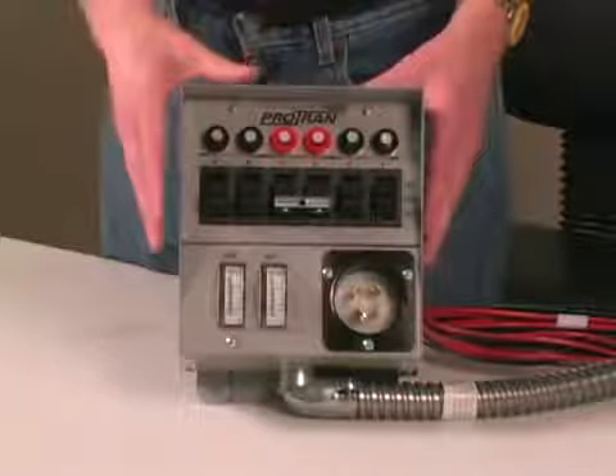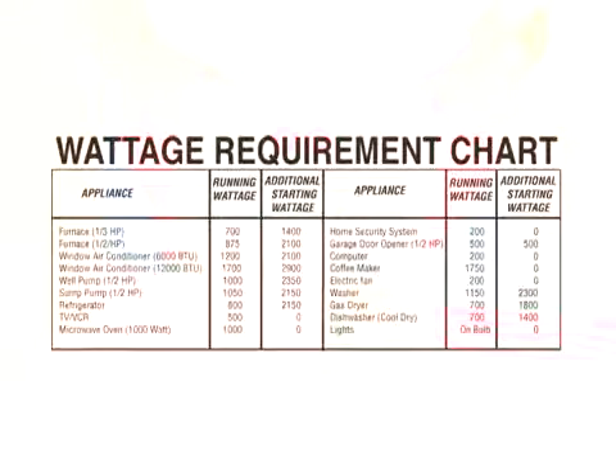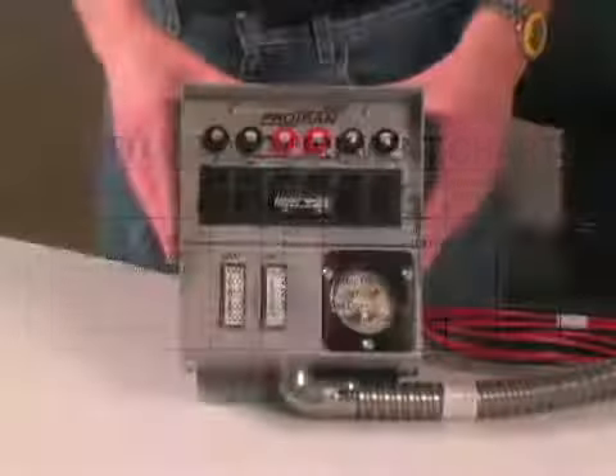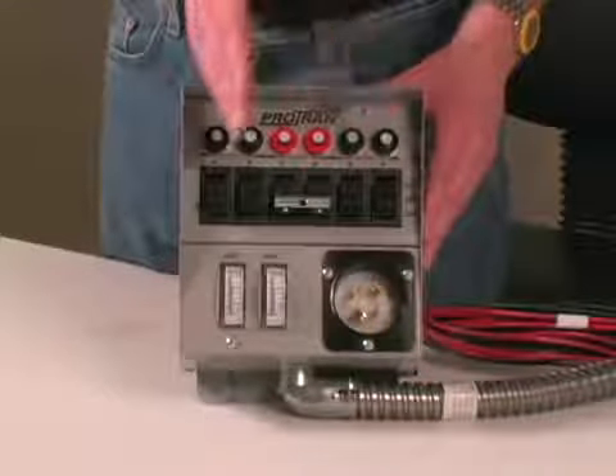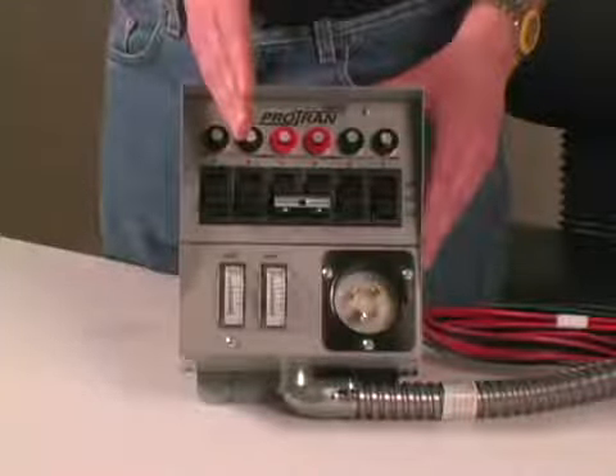There is a chart in your installation manual that shows the wattage requirements for some typical household devices. When choosing which circuits to operate, try to divide the total wattage evenly between the 2 sides of the transfer switch. Be sure to refer to your installation manual for more details on load balancing.